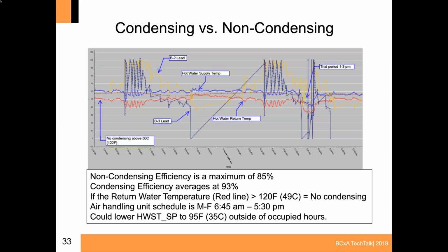So if you can get below that, which you do see it dipping below that 50-degree line at times, then we can get our boiler plant efficiency up to a condensing efficiency of 93%. And in the trial period, you can actually see where when we made the adjustments to the supply water temperature set point, we dropped down well below that and had condensing throughout that trial period.